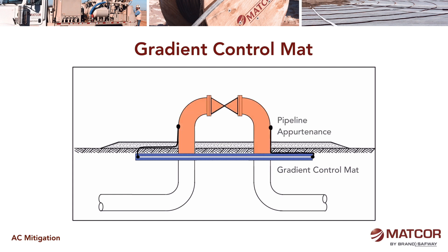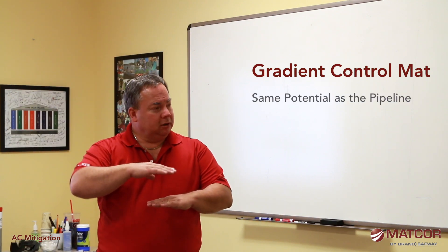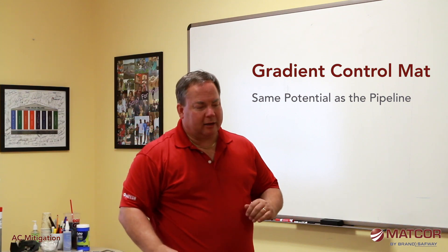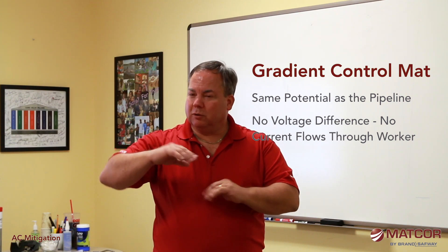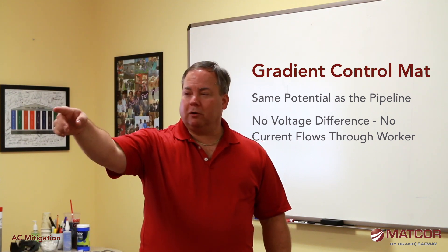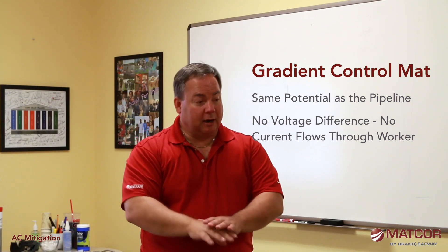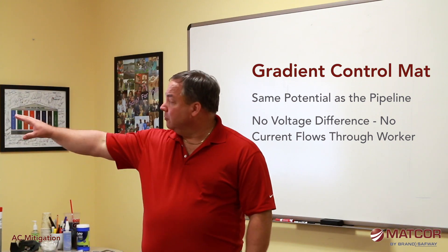A gradient control mat is a simple device connected to the pipeline at an appurtenance where someone can touch it, extending out around that appurtenance enough so that somebody standing on it is not within the step potential. Because it's connected to the pipeline, the whole gradient control mat is at the same potential as the pipe. As soon as I step onto that gradient control mat, I don't have a voltage difference between me and everything else — even if I touch the pipe, the ground below me is also at the same voltage as the pipe, so no current will flow through my body.